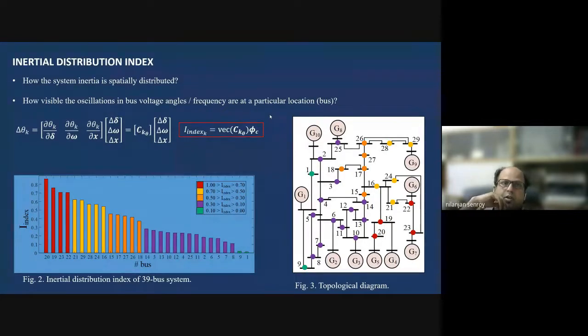So if you have a low inertia index, then the grid is likely to show very big oscillations, while if you have a very high inertial index, then the grid is likely to be very, very stable. The frequency and the voltage angles would be very stable. So these are all related to the active power. Right now, they can be extrapolated to the reactive power also. I invite all of you to have a look at that and see how this can be extended to include the reactive power components also.